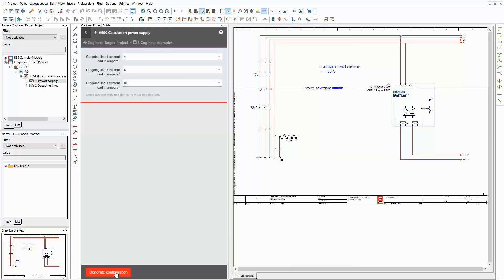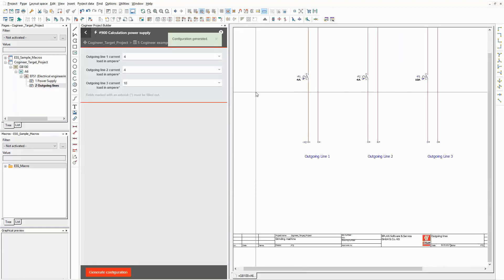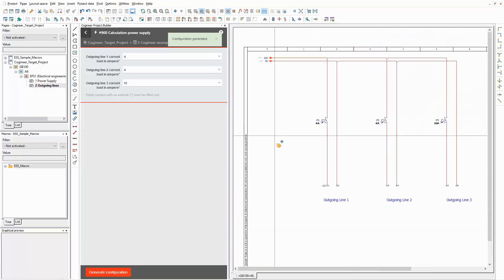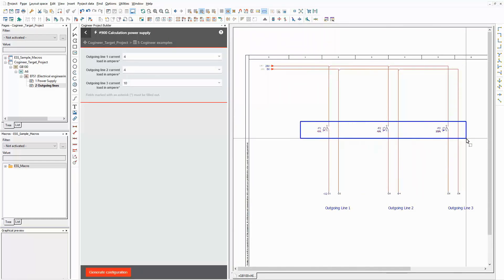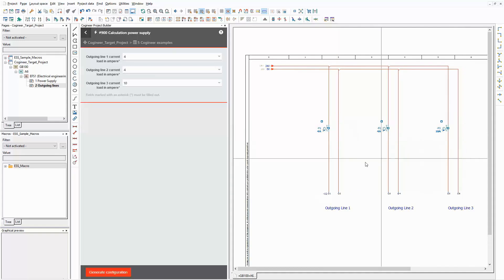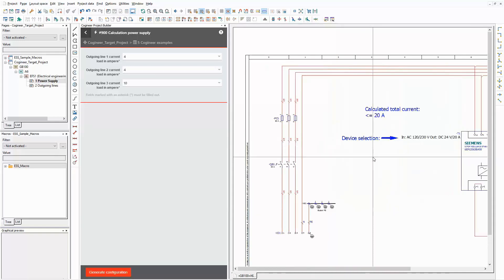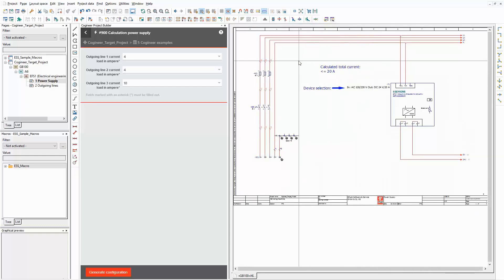Depending on the sum of the current loads, a part is chosen automatically for the power supply unit that can handle the accumulated current load. As you can see on this page, the new values are now used for the circuit breakers. The sum of the current loads is 18. As you can see on the other page, the power supply unit changed. It can handle up to 20 A.